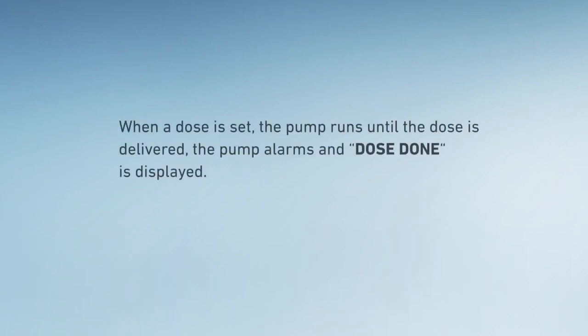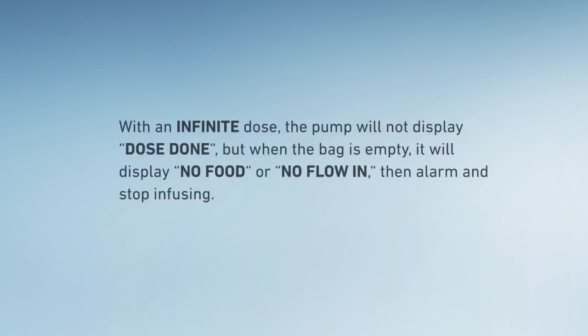When a dose is set, the pump runs until the dose is delivered, then alarms and dose done is displayed. With an infinite dose, the pump will not display dose done, but when the bag is empty, it will display no food or no flow in, then alarm and stop infusing.